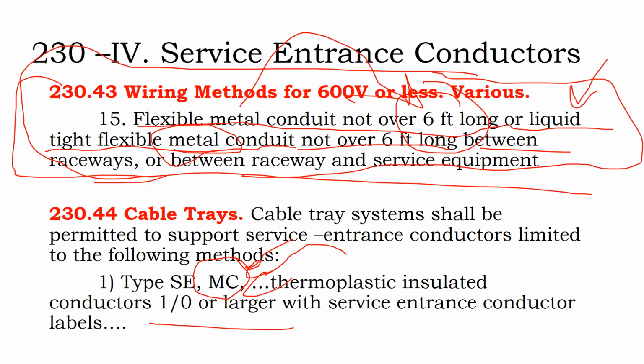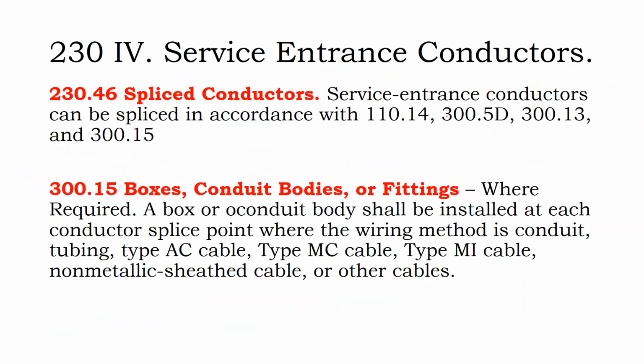So this is more just saying flex metal conduit is not a really good thing to use over 6 feet long. There's a reason why this rule is in code, and it's a safety reason. We could research it and find out what that safety reason is, or we can take them at their word and just say, for some reason, we shouldn't use flex conduit that's more than 6 feet long, and it's a more expensive way to do things anyway. There are other, better solutions out there, such as metal clad cable, where you would have the runs being longer than 6 feet.